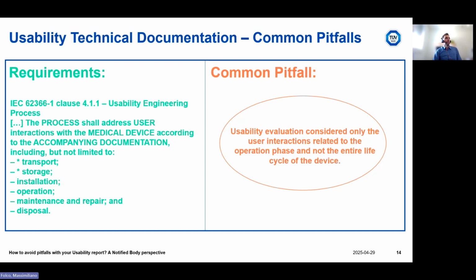Common pitfall: usability evaluation considers only the user interactions related to the operation phase and not the entire life cycle of the device. In this case, something is missing in the usability evaluation. Not all the use interactions have been considered, and maybe not all the intended users have been considered. For example, transport people, installation people, maintenance people, and so on.